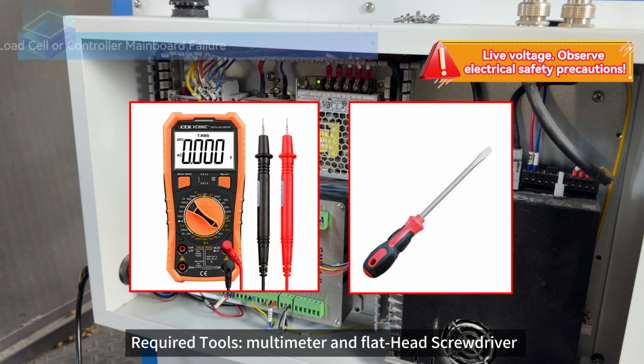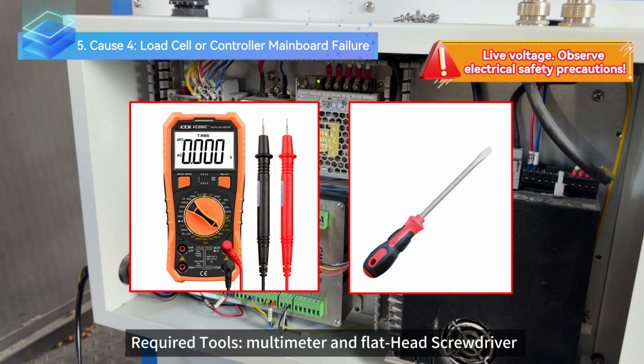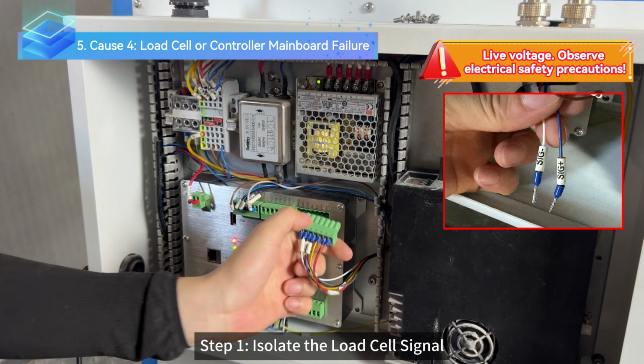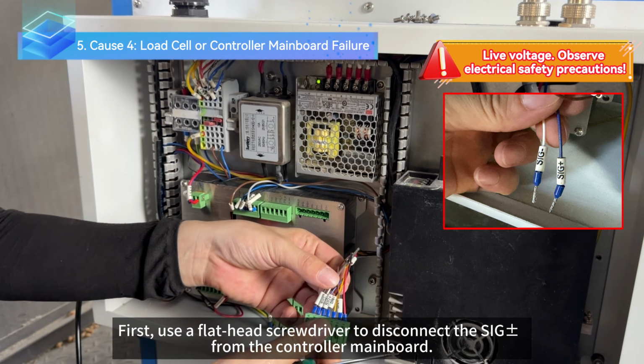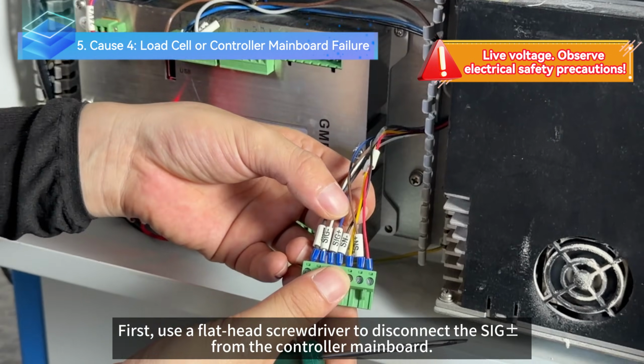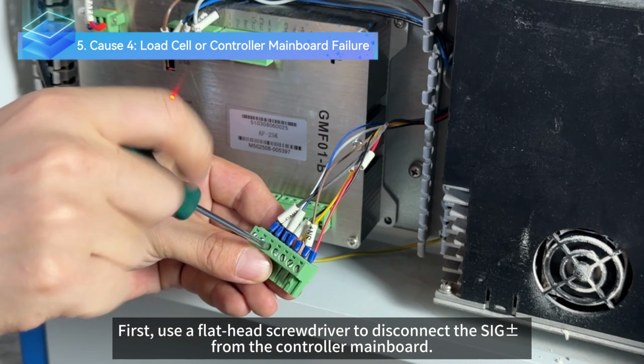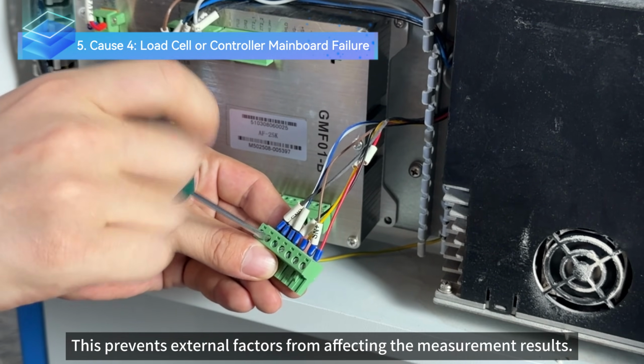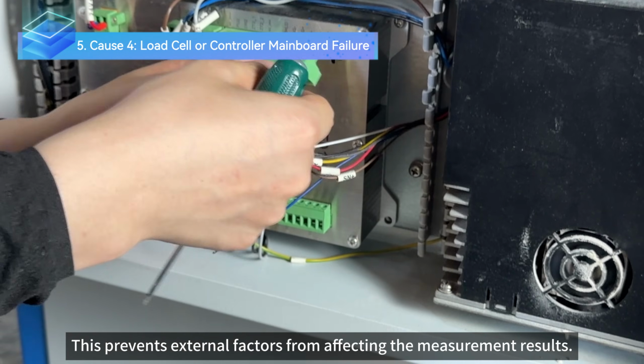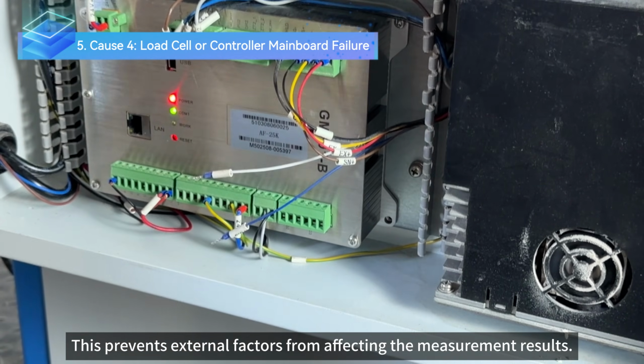Required tools: multimeter and flathead screwdriver. Step 1. Isolate the load cell signal. First, use a flathead screwdriver to disconnect the SIG plus and minus from the controller mainboard. This prevents external factors from affecting the measurement results.